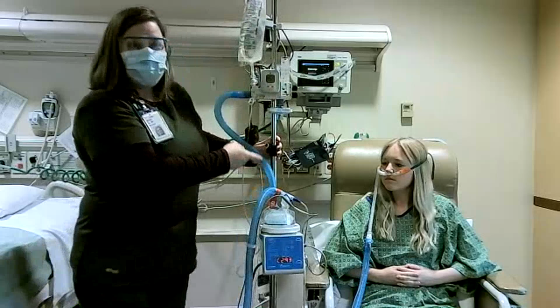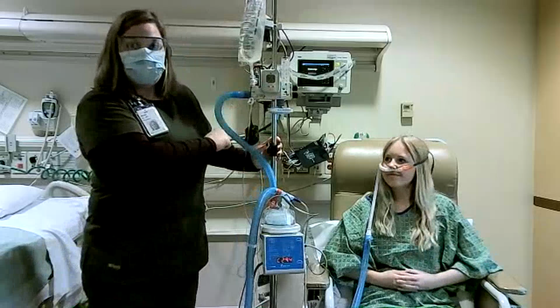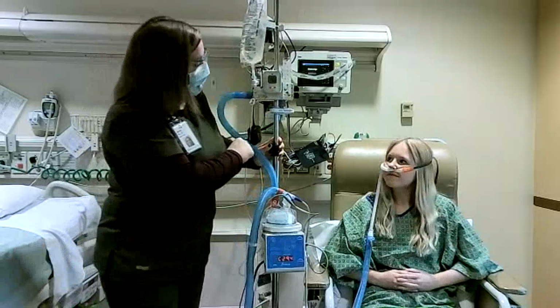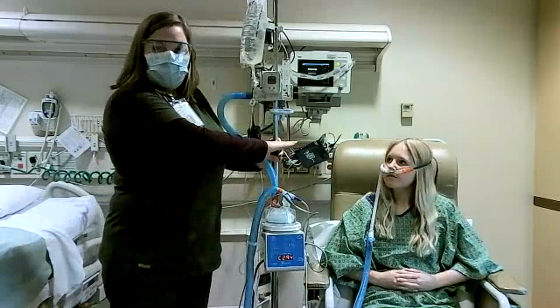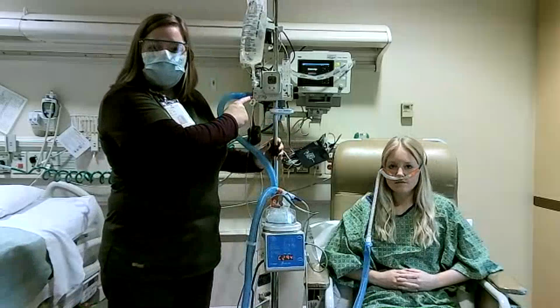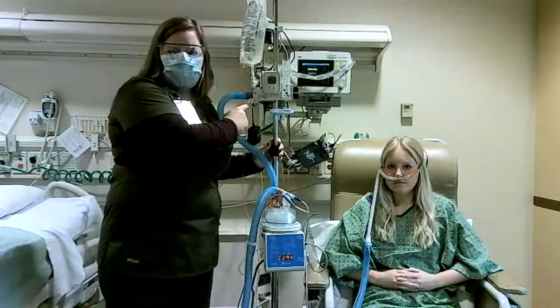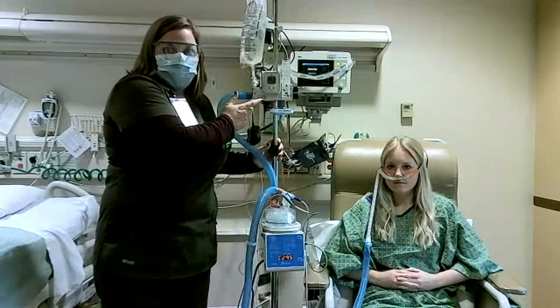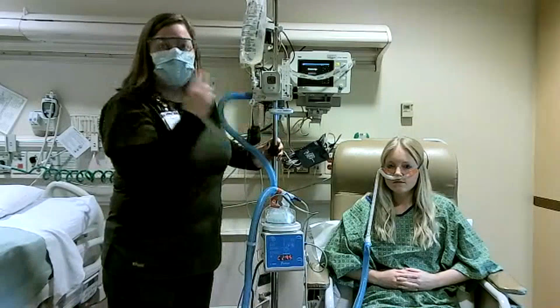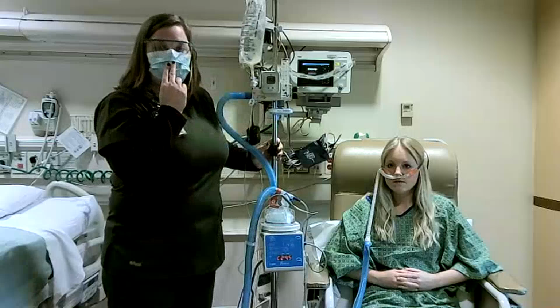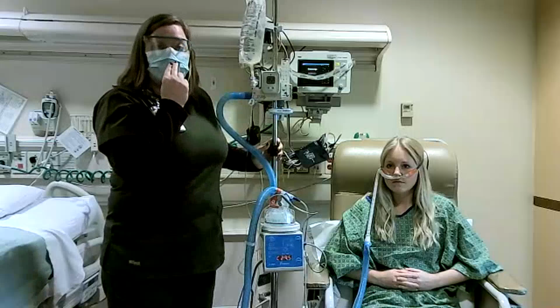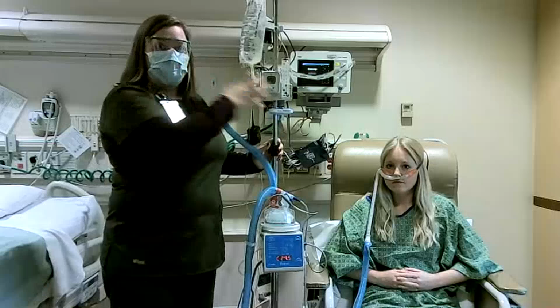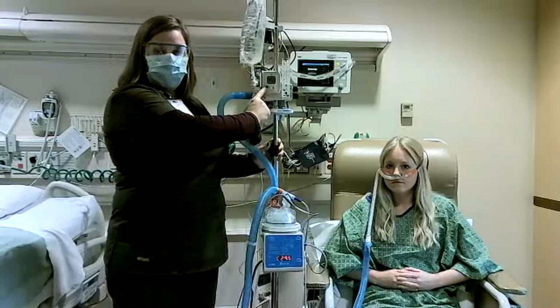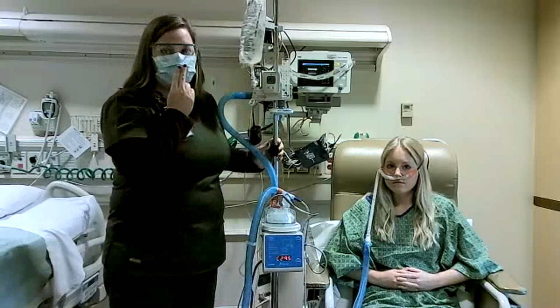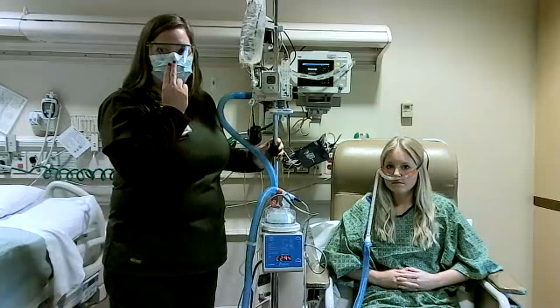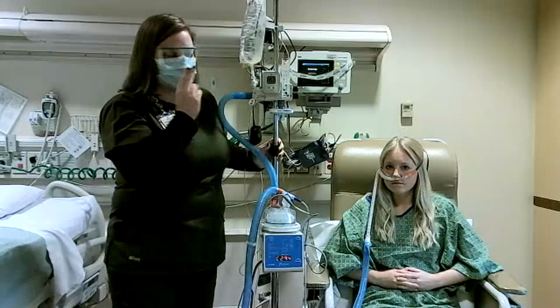So this is our patient, Jenny. She is doing better today. She's been with us for a few days now. And her nasal cannula is on. If you walked in the room and maybe you thought you were set at 60%, now you see you're reading 70 or 75 or 80%, check that cannula. Make sure it's still sitting pretty neutral in the nares. If it's pinching, it can build up a backflow of oxygen and come back into your machine and read a little bit higher. So make sure that that's sitting kind of neutral in the nares if that's a change that you're noticing.